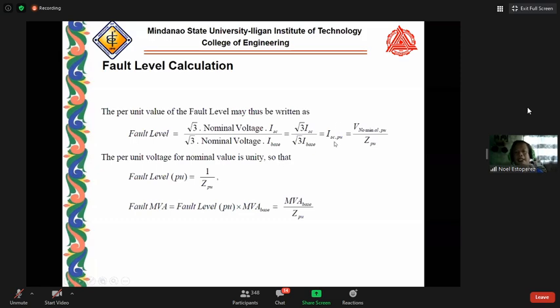We have here square root of 3 times I fault per unit. In terms of the impedance, the fault level in per unit is 1 over Z per unit, which is simply the fault MVA, equal to the fault level times the MVA base. So usually what we look at here is the per unit impedance of our utility. If we cross multiply this with the fault MVA, our Z per unit will be MVA base over the fault MVA. We need this in our solution.